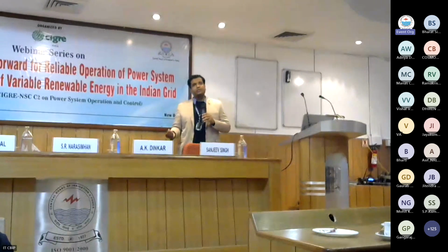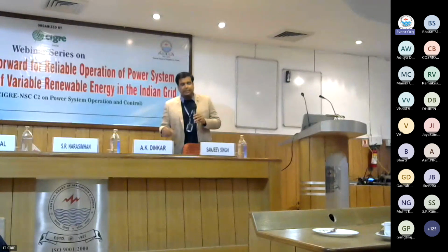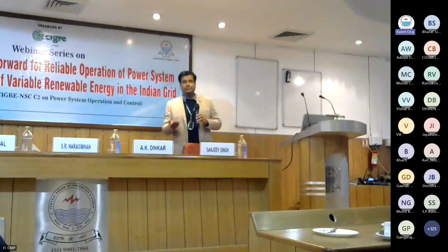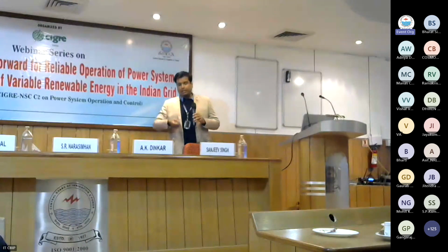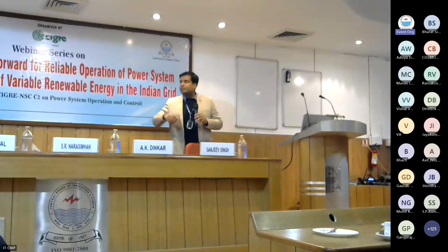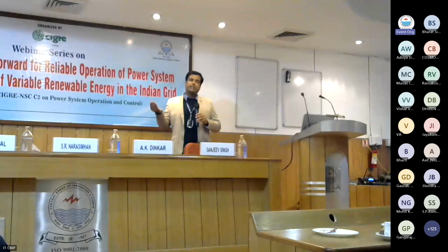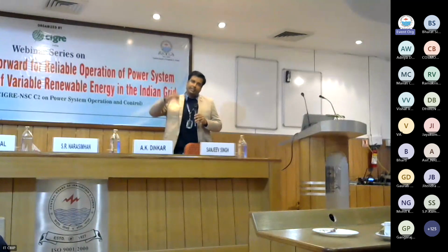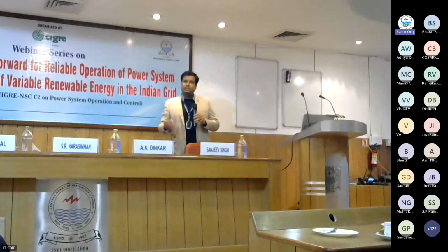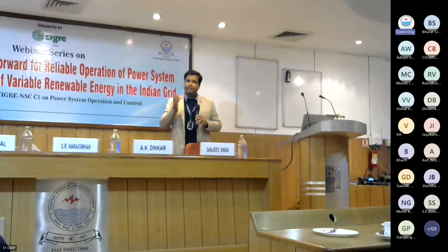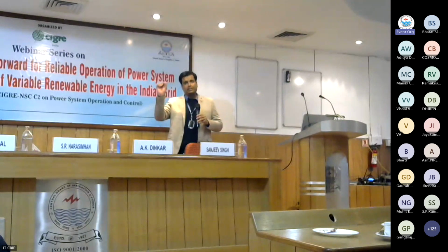After the reduction of generation, the behavior was not satisfactory. What was expected of them as per the CEA standard, they were not able to inject the reactive power or to restore their generation within 1 second. That resulted again in a very high voltage, and during that high voltage, plants again entered the high voltage ride-through zone and reduced their generation. This way, severe high voltage got built up, and the evacuating lines tripped on the over voltage stage 1 protection. Then the voltage came down, and after that, plants started.